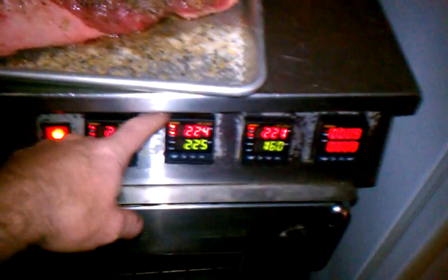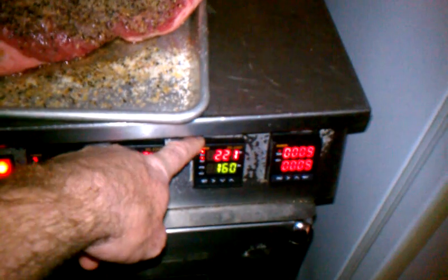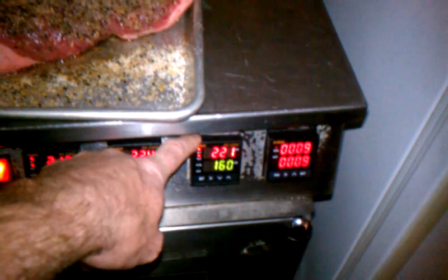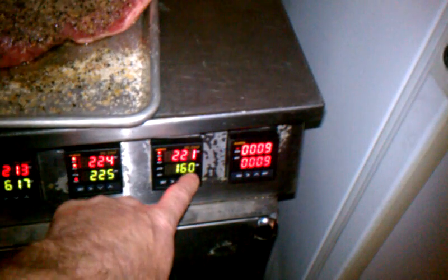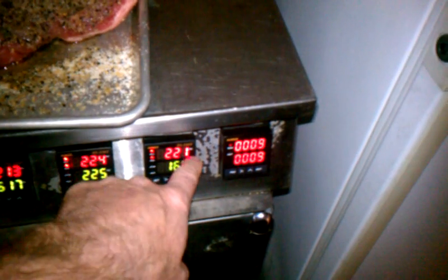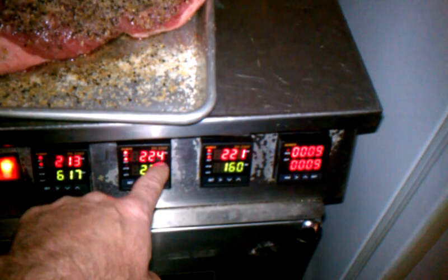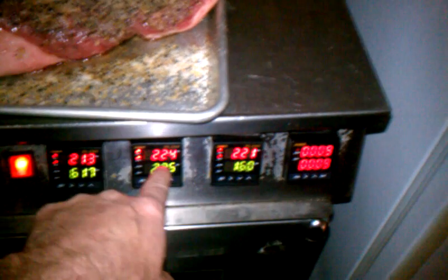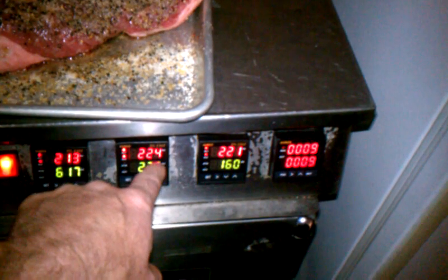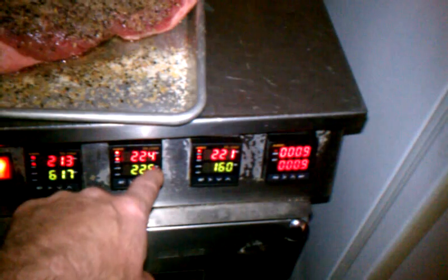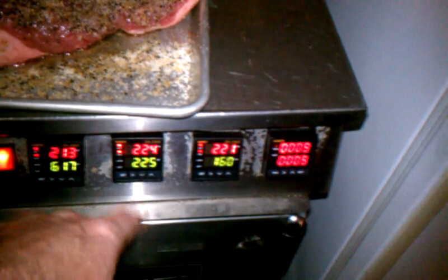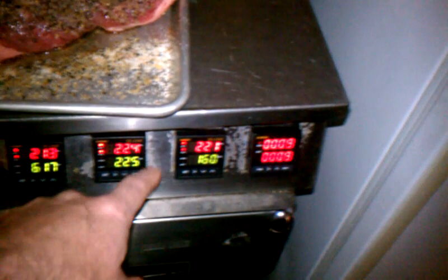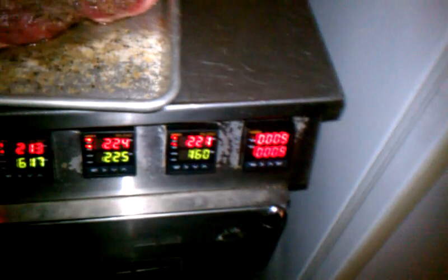So that's the main oven temp, and then this is the oven hold thermostat, or PID. I've got it set at 160, even though the value is reading at 221 right now. A little bit of difference, not too much, between the thermocouples - both the same K-type thermocouples, reading about 3 degrees off. They're placed within about an inch of each other, so I guess that's an acceptable difference.